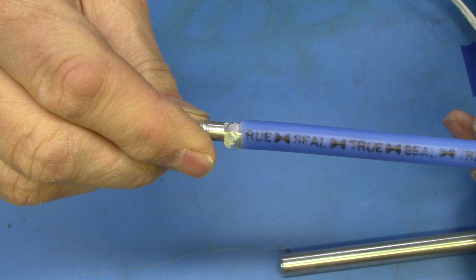Now, there should be a 1/4 inch deep empty cavity at the other end of the polypropylene tubing. Using the hot glue gun and starting deep into the cavity at the end of the polypropylene tubing, completely fill the cavity and then let it cool. The purpose for this is to deny a viable high voltage arc path between the end of the aluminum rod and the aluminum tubing, which surrounds the poly tubing.